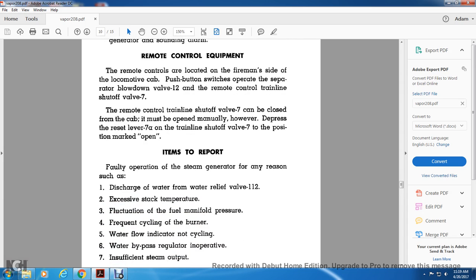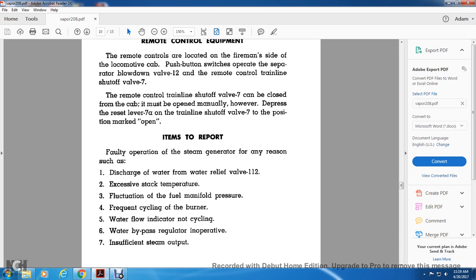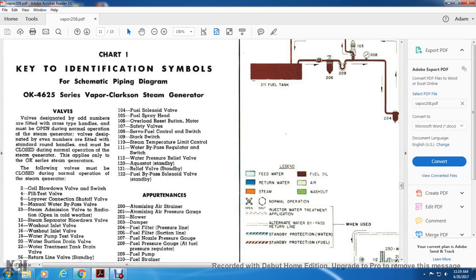Items to report: faulty operation of the steam generator for any reason, such as discharge from the water relief valve 112, excessive stack temperature, fluctuation of fuel manifold pressure, frequent cycling of the burner, water flow indicator not cycling, water bypass regulator inoperative, insufficient steam output. Alright, and then we move on to chart 1.